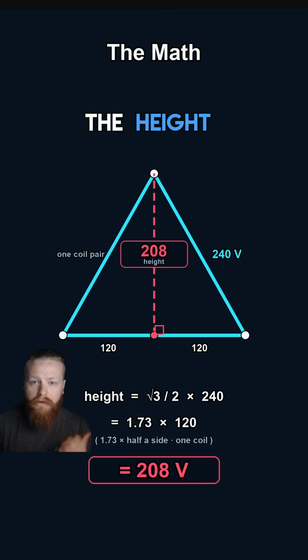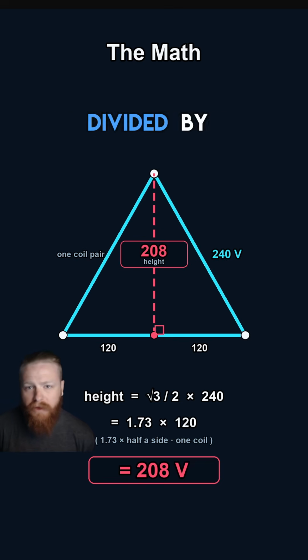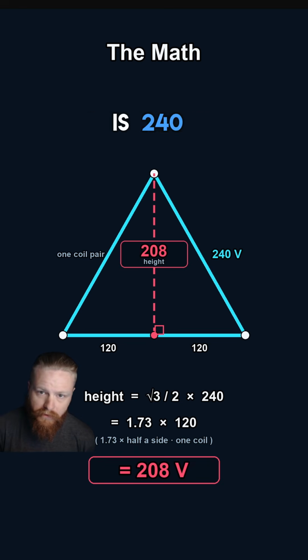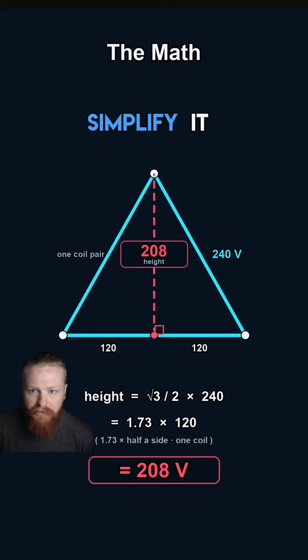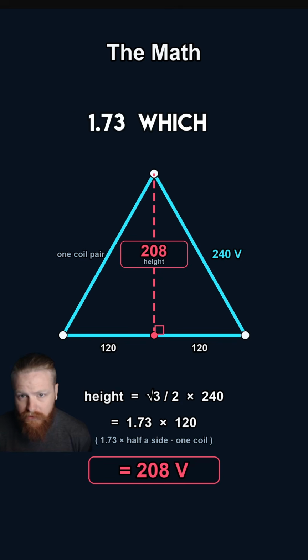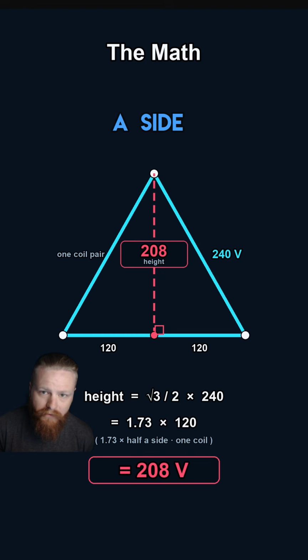So let's calculate the height. The formula is the square root of 3 divided by 2 times the length of one side, which is 240. But that's a little confusing, so we can simplify it down to 1.73, which is the square root of 3, times half a side, or one coil rating. 1.73 times 120 is 208. And that's the wild leg.